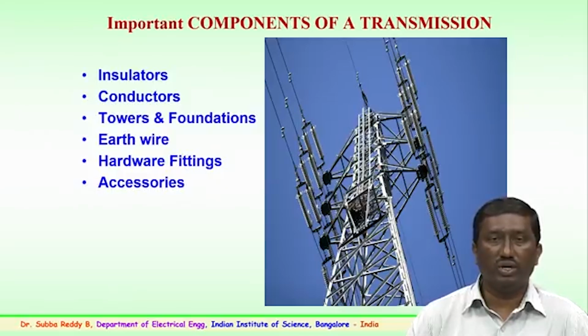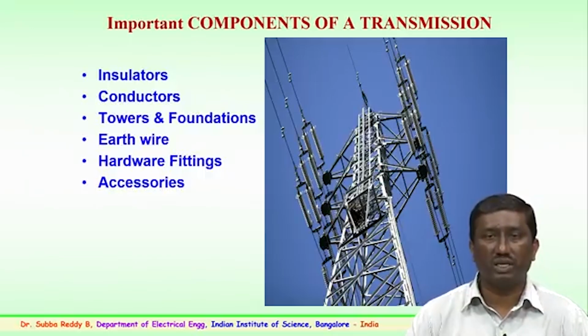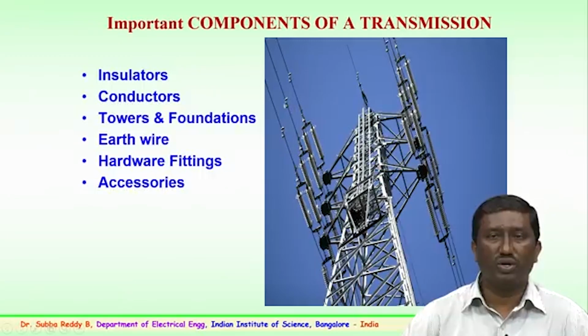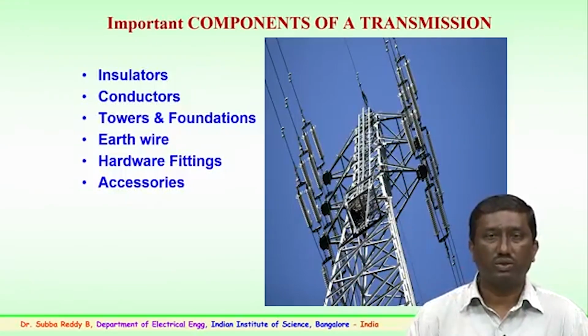And finally, an important component is the accessories. There are various types of accessories which most engineering students would not have known. The accessories are a very important part of any transmission system. When you go near any transmission system, you see small components here. These are nothing but the vibration dampers. Similar to the vibration damper, there is a specific component which controls the damping of oscillations; we will look into the importance of the vibration damper. Few accessories like mid span compression joints, repair sleeves, T connectors, many of these fall under the accessories. So, these are some of the important components of an ultra high voltage transmission system.